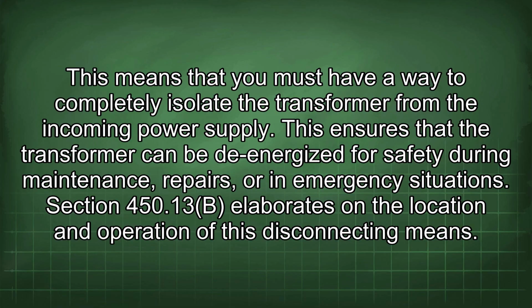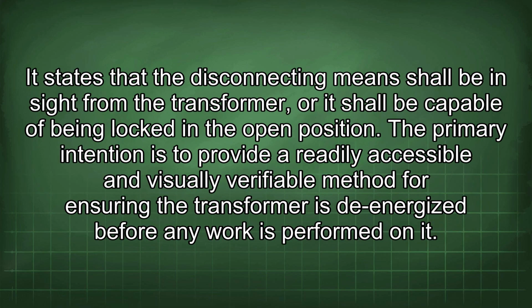Section 450.13b elaborates on the location and operation of this disconnecting means. It states that the disconnecting means shall be in sight from the transformer, or it shall be capable of being locked in the open position. The primary intention is to provide a readily accessible and visually verifiable method for ensuring the transformer is de-energized before any work is performed on it.